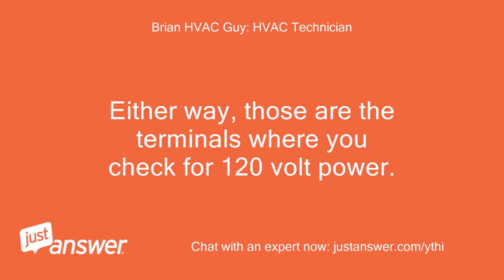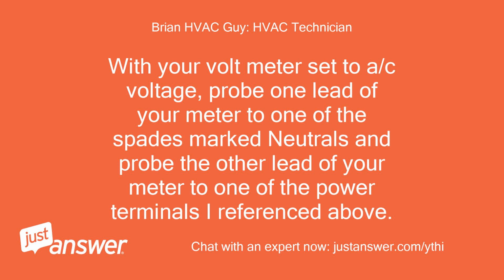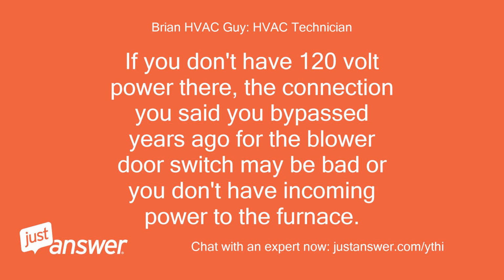Either way, those are the terminals where you check for 120 volt power. With your voltmeter set to AC voltage, probe one lead of your meter to one of the spades marked neutrals and probe the other lead of your meter to one of the power terminals I referenced above. If you don't have 120 volt power there, the connection you said you bypassed years ago for the blower door switch may be bad, or you don't have incoming power to the furnace.